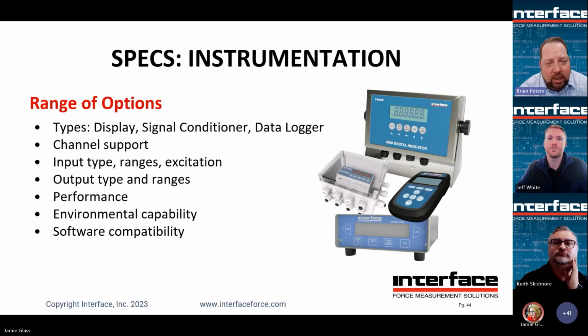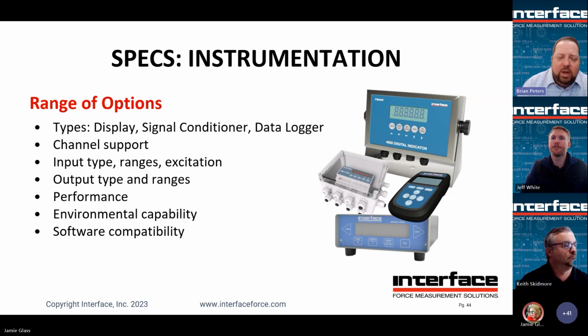Many of these have throughputs or outputs. So then it'd be a function of understanding and looking at the specifications around the output types. Is it a straight through? Is it scalable? Is it not scalable? Does it have the analog or digital output specifically that you're looking for? Then there's the performance specs. Those are pretty straightforward. Performance specs will vary a little bit from unit to unit in terms of what's listed or what's tested. Then the environmental: does it have adequate IP? Is it splashdown rated? Does it need an enclosure? And then the software compatibility. So again, these can tie often to different software, whether it's to capture the data or to further enhance the measurement capability of that sensor or the instrument, excuse me. Next slide.